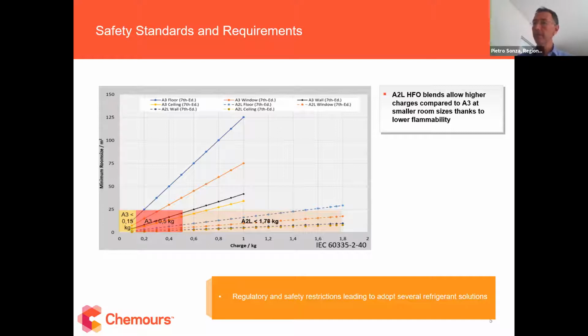So this chart shows, in essence, the regulatory requirements for A2L refrigerants and A3 refrigerants in the kind of applications we have explained so far, and also the limitations of refrigerants which, as we said, carry excellent thermodynamic properties but have, on the other side, safety concerns, while A2Ls can cover that from another perspective. So although the thermodynamic properties are not equal to those of propane, they carry this mildly flammable behavior, which makes them safer and allowed to be used in larger quantities, larger charges, for different applications.